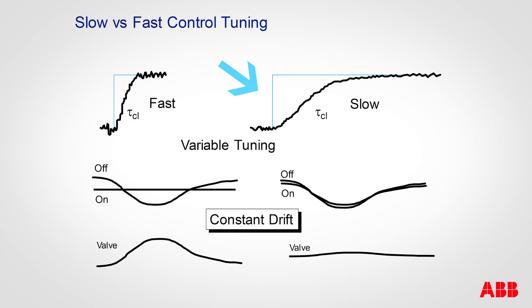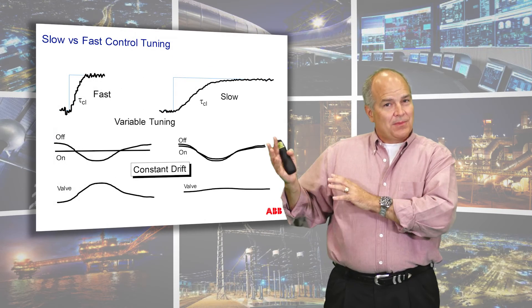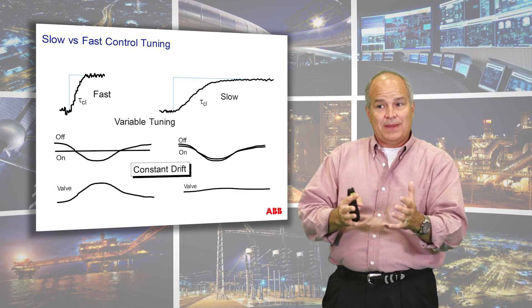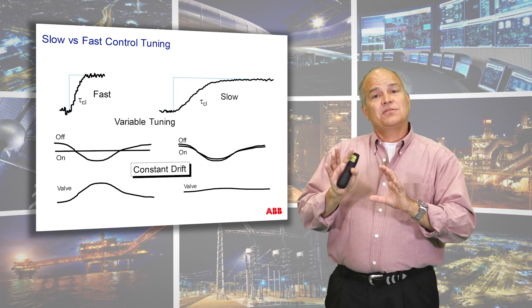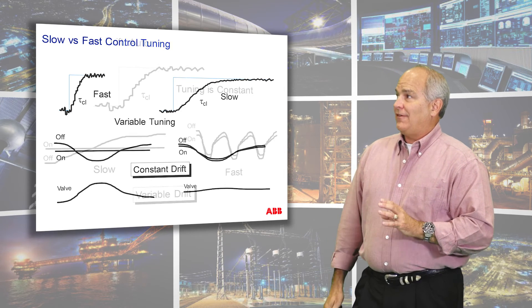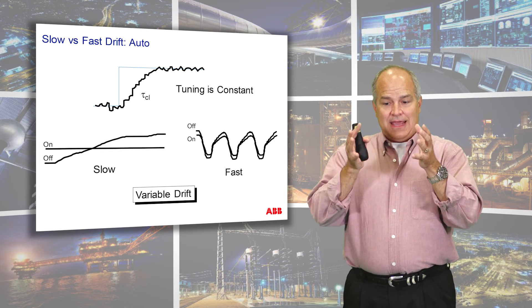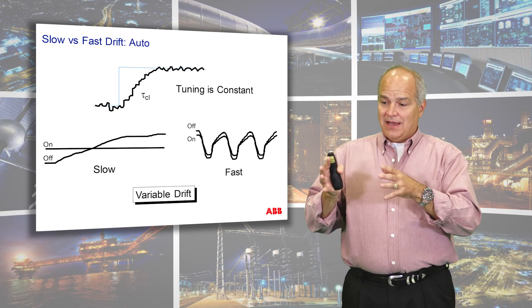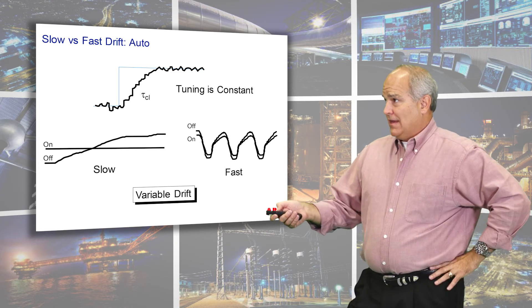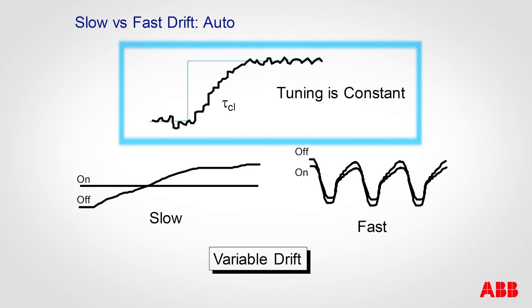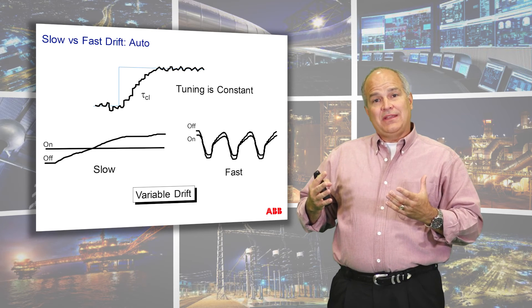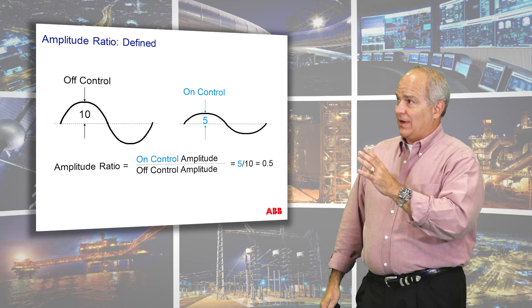If I've tuned it slow, the energy just passes right through. Remember our example of the tank at low level and high level — it's exactly the same kind of thinking. Does that energy pass through or does it get absorbed in the process? Very rarely do you have different tuning; you usually have a tuning with different frequencies, and this is where we're getting into frequency decomposition, spectral overlay and all that kind of neat stuff. With a single control tuning, I have a low frequency drift and a high frequency drift. As that frequency changes, your ability to attenuate that frequency drops off, and that's where the amplitude ratio comes in.